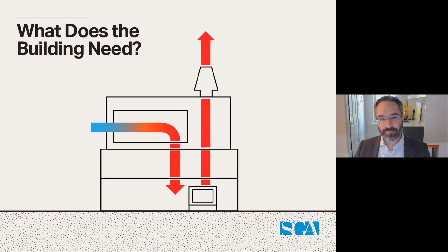The first thing you can do to reduce this load is use less air. Hopefully all of you have fume hoods approaching the 50 feet per minute face velocity. You've got self-closing sashes, and we're getting out of the habit of storing chemicals in hoods that could be in chemical storage cabinets. Everything you can do to reduce the amount of air flowing through those hoods reduces the size of the air handler and the amount of energy you have to use to condition the air.